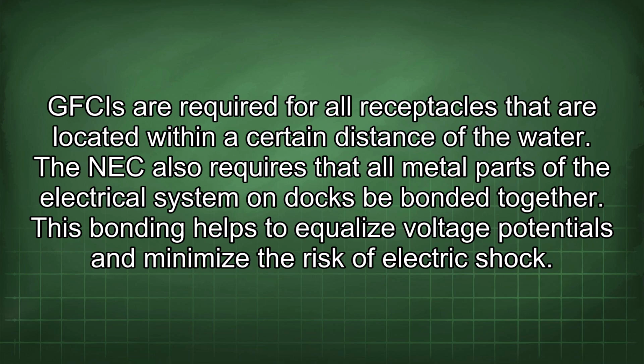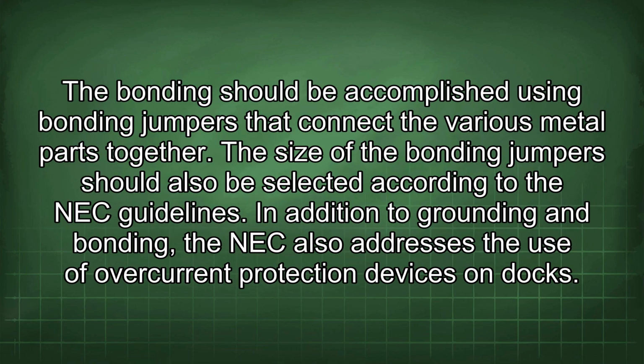The NEC also requires that all metal parts of the electrical system on docks be bonded together. This bonding helps to equalize voltage potentials and minimize the risk of electric shock. The bonding should be accomplished using bonding jumpers that connect the various metal parts together. The size of the bonding jumpers should also be selected according to the NEC guidelines.